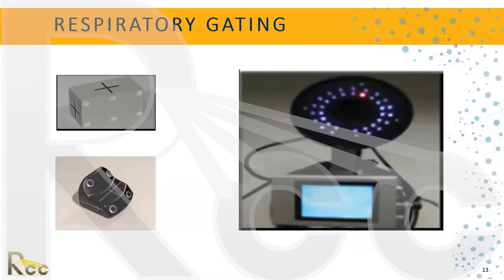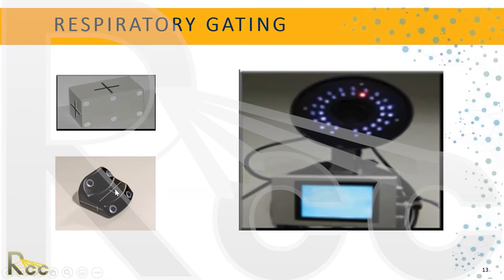What's involved with respiratory gating? We need tools and equipment. One key piece is an infrared camera mounted on the wall — it emits light. The other is a marker box placed on the patient. When the camera emits light, the reflector dots on the marker box reflect it back, and the camera captures what we call a respiratory signal to track and analyze the patient's motion. There are different vendors with different software for this.